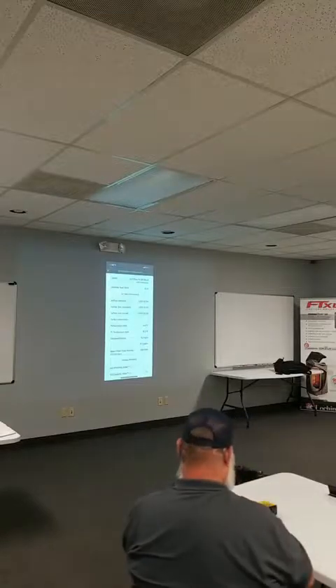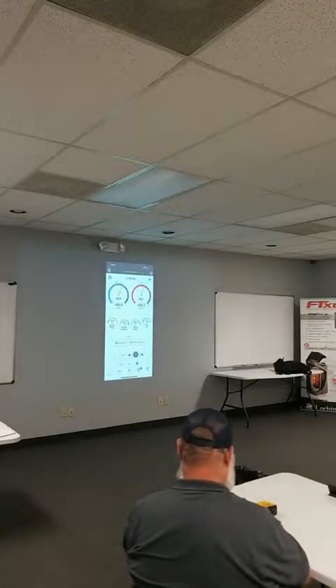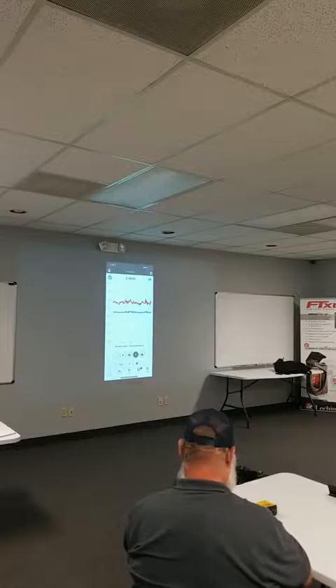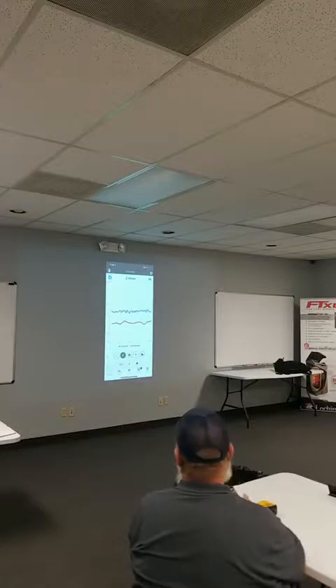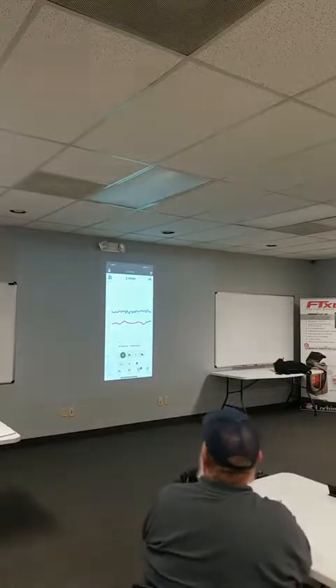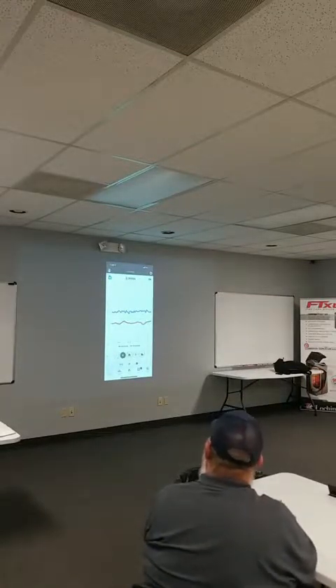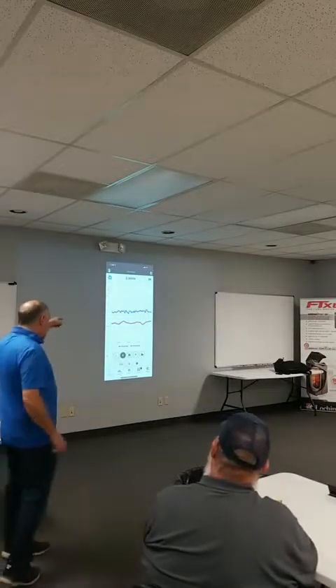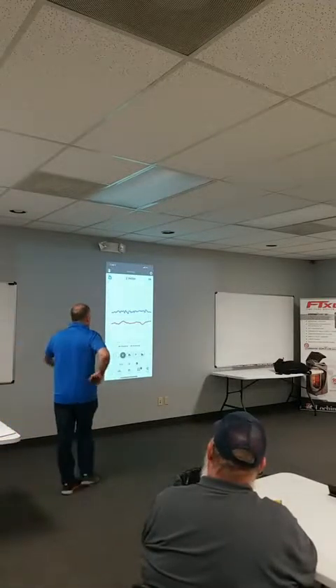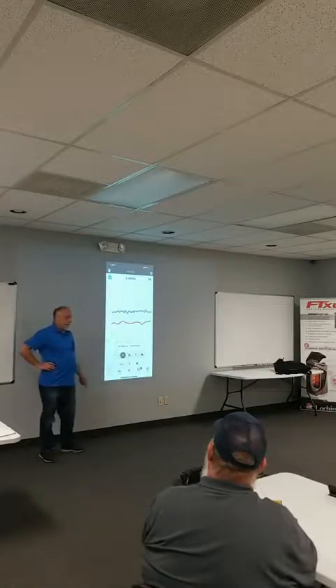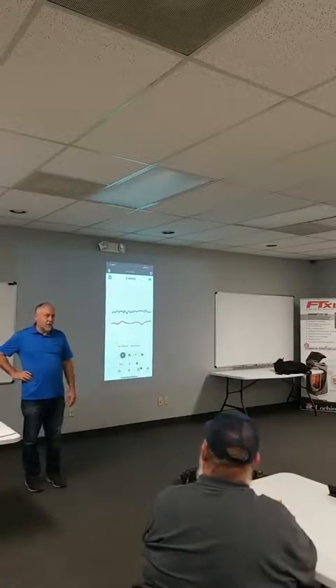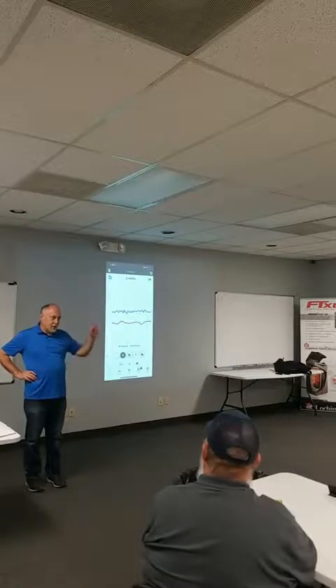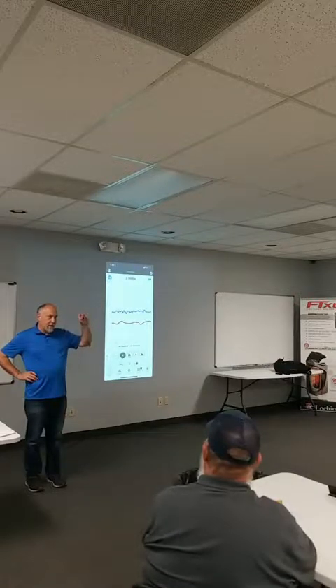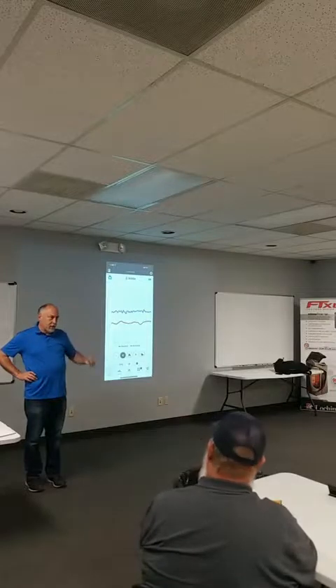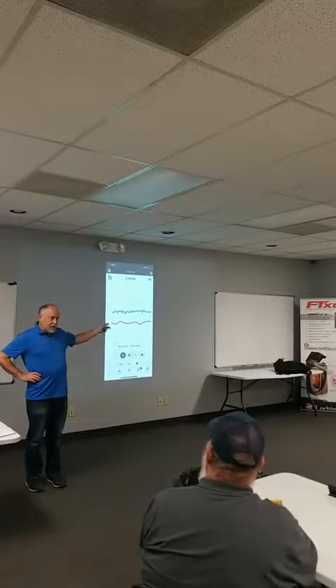Once you start watching the stuff, you see it all happen in real time, and you see things like the trending. So working at our total capacity trends, we can look at what our subcooling's doing here real quick. So here's our superheat and our subcooling, right? That's the valve modulating, so your subcooling actually is changing. Anybody know why this is changing a little bit? What happens every time the valve opens or closes? What happens to the head pressure? The head pressure drops when the valve opens, and when the valve closes, the head pressure goes up. You're actually seeing the impact of the valve modulating on the high side.